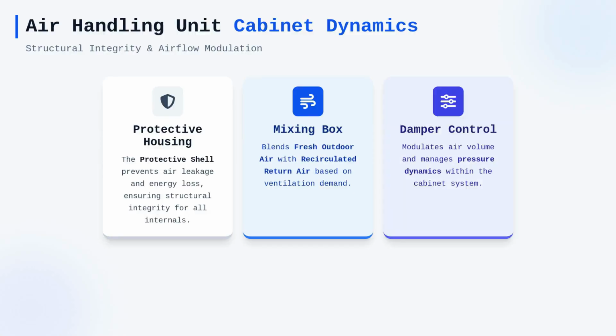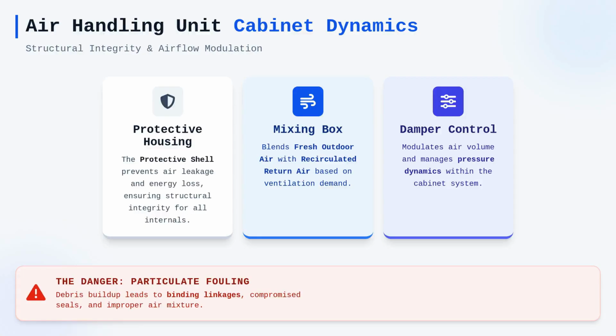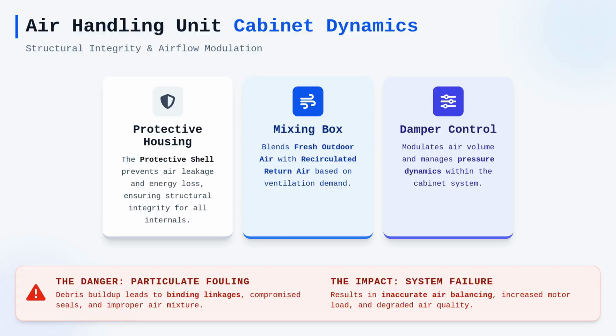Dampers are positioned at these intake points to modulate the volume of air entering the system, directly influencing the pressure dynamics within the cabinet. If these dampers become fouled with particulate matter, their ability to seal or modulate airflow is compromised, which often leads to inaccurate air balancing and increased motor load. Technicians must observe the condition of these linkages and actuators because even minor debris buildup can cause binding and improper air mixture, directly affecting the conditioned air quality.